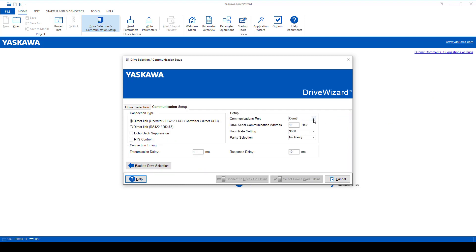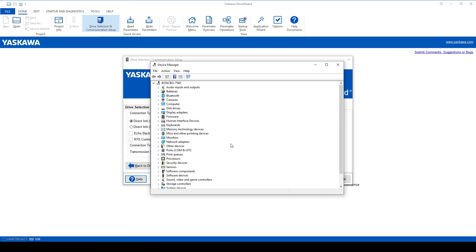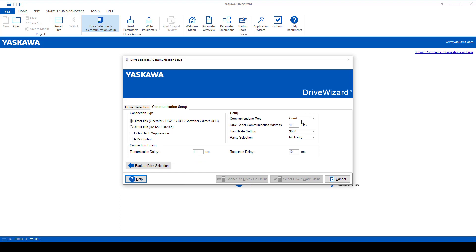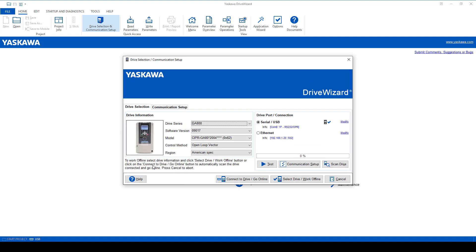If you have difficulty connecting using the USB serial connection, verify that you're using the correct COM port. To do this, you simply go to your computer, select Device Manager, and then look at the COM port selection. The COM port that your USB cable is plugged into on the computer should appear. Usually, it identifies the Yaskawa name in that same port.